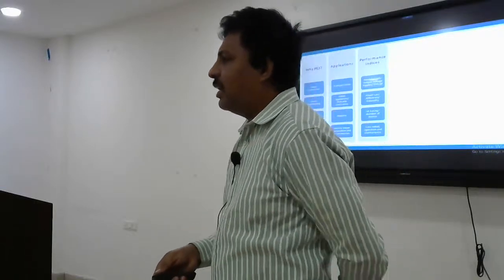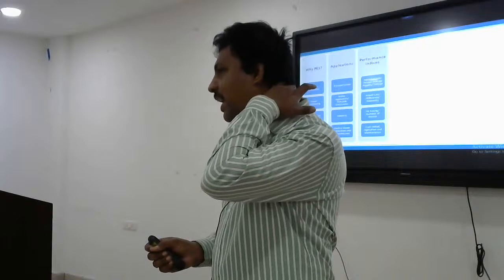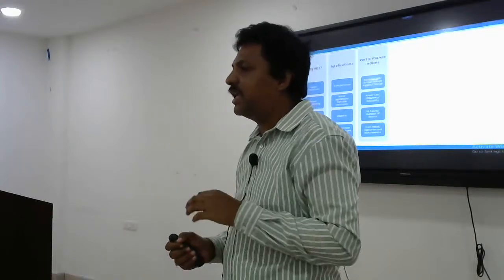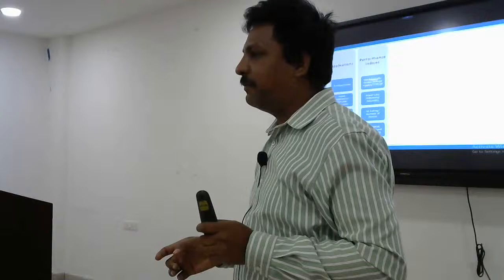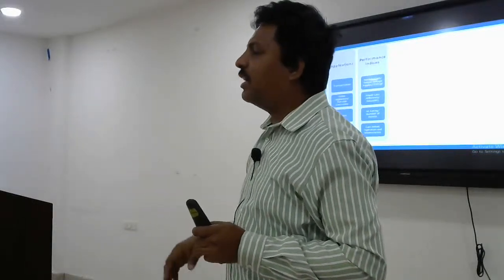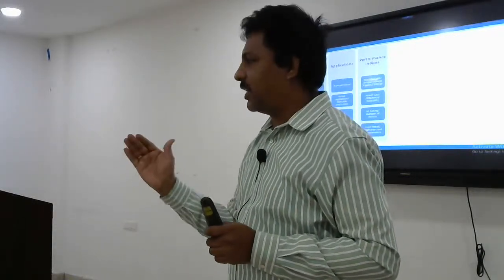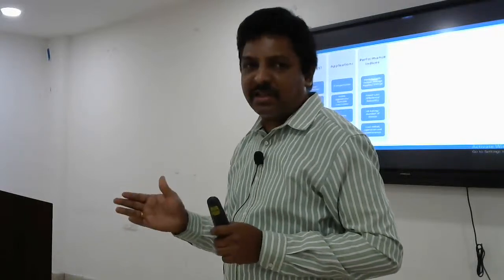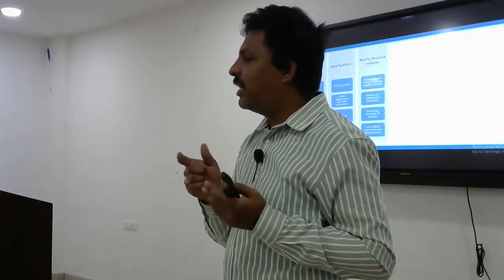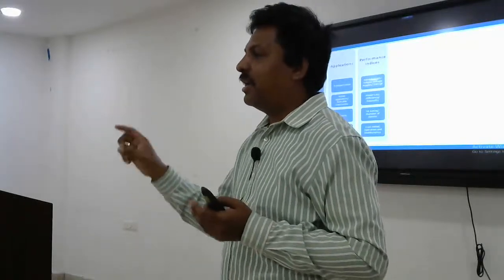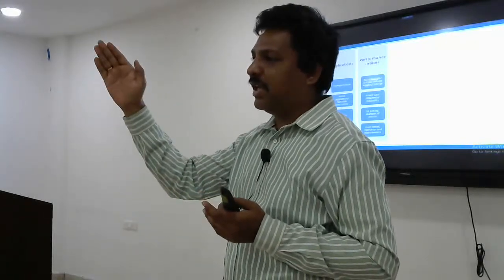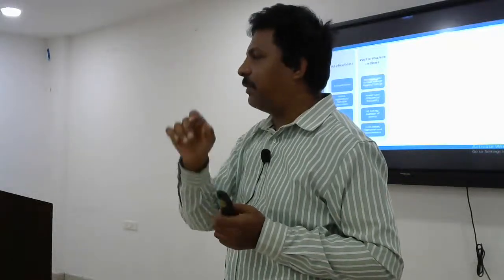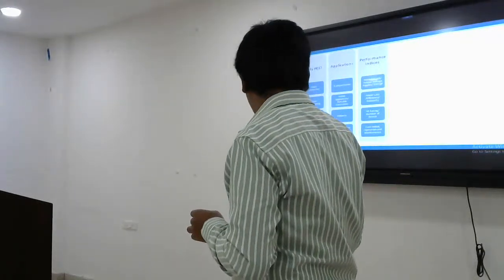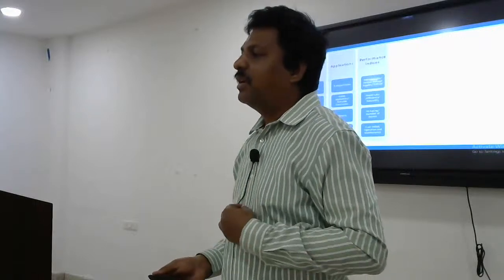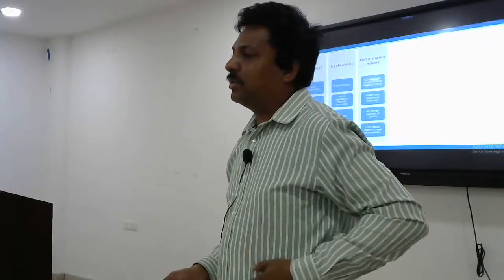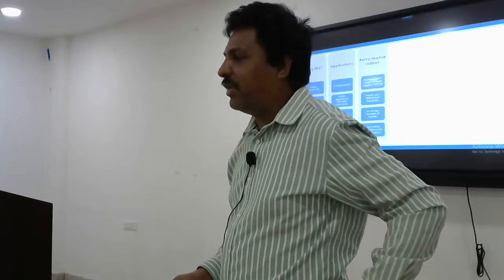For example, the load is demanding I plus IH, where IH is the harmonics and I is the fundamental component. If you locally give IH in the reverse direction, then the current coming from the grid is only I, because IH is cancelled. That means this power conditioning equipment is used for cancelling harmonics also. Technically, they are named as active shunt filter.